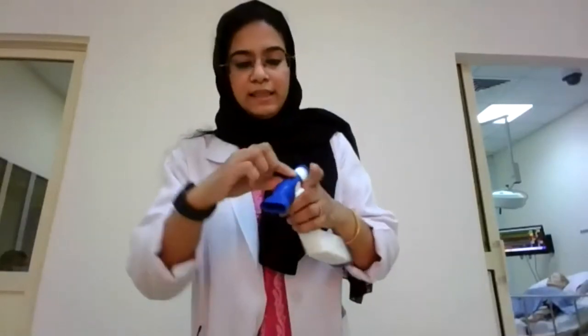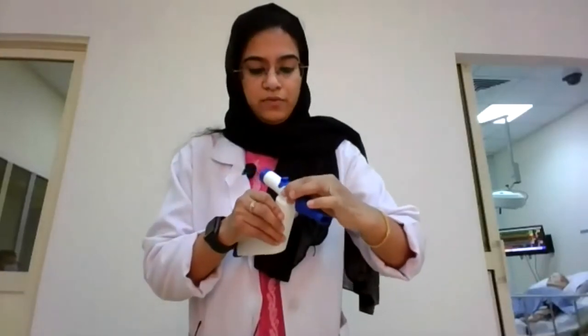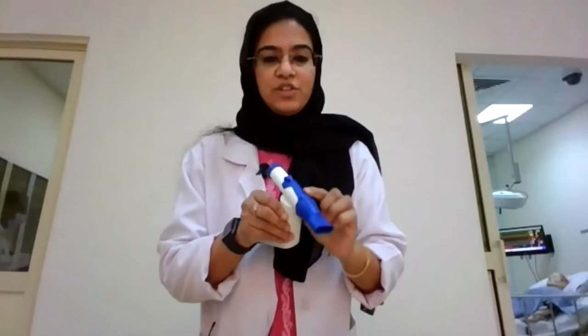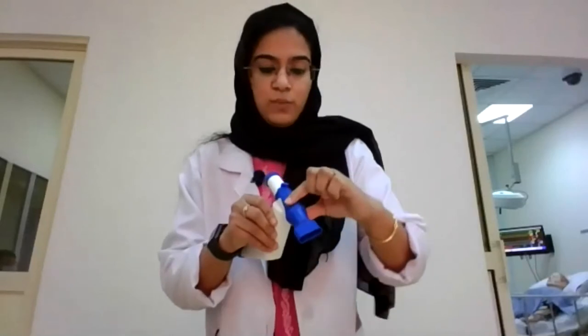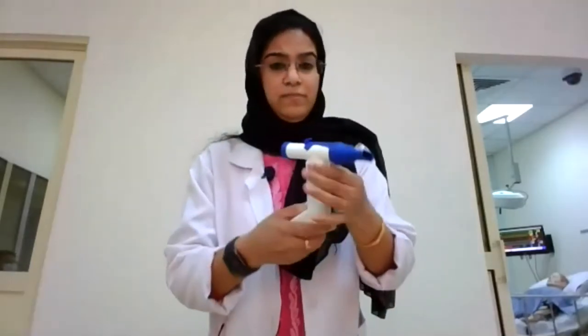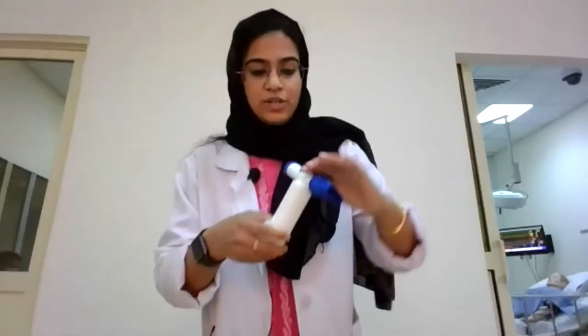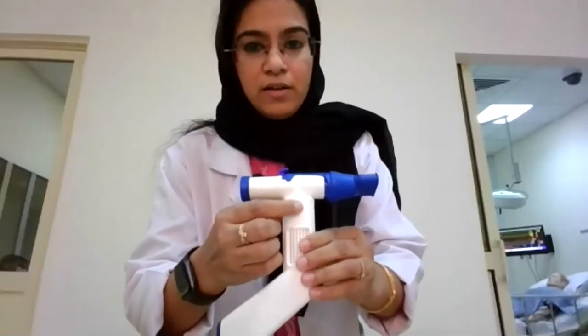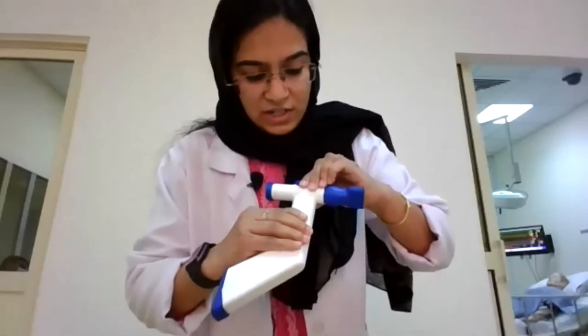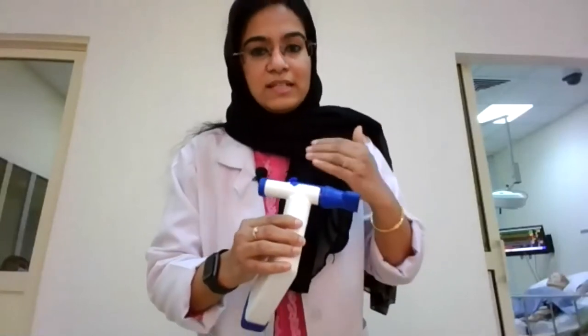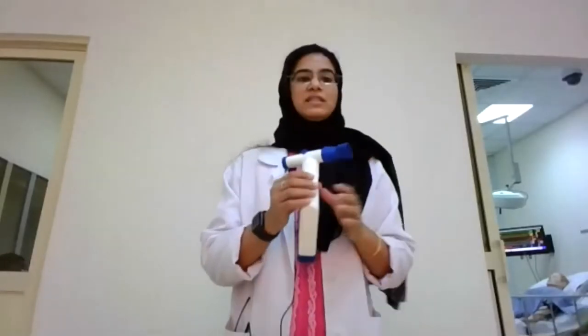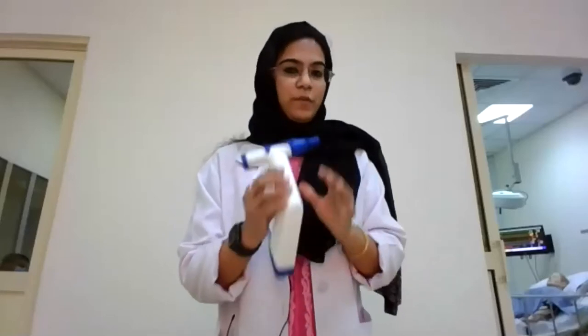And this is the RC Cornet Plus, which also consists of a mouthpiece. There are two mechanisms here. One here is the resistance, which can be managed. This is essential for those patients who have breathlessness. So in order to reduce breathlessness, we can manipulate this part, and to increase the oscillations, we increase the amount of resistance. Here you can see a mark which will determine the resistance. When we change it from lower to higher, the amount of resistance will increase and ultimately the patient has to breathe against this high resistance. This can also be used for pediatric patients because they find it very handy and like to use these kinds of devices. This device has an extra advantage that it can be connected with the nebulizer.